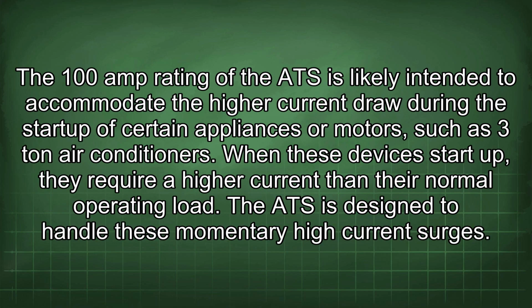The 100 amp rating of the ATS is likely intended to accommodate a higher current draw during the startup of certain appliances or motors, such as 3-ton air conditioners. When these devices start up, they require a higher current than their normal operating load. The ATS is designed to handle these momentary high current surges.